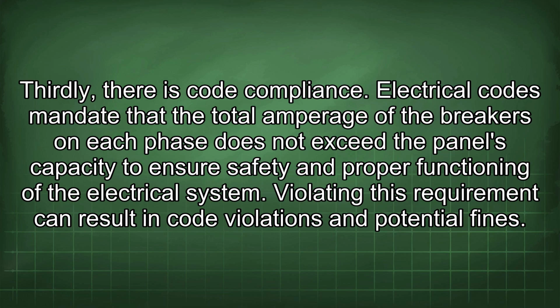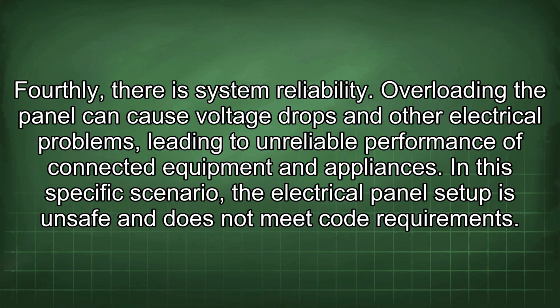Electrical codes mandate that the total amperage of the breakers on each phase does not exceed the panel's capacity to ensure safety and proper functioning of the electrical system. Violating this requirement can result in code violations and potential fines. Fourthly, there is system reliability. Overloading the panel can cause voltage drops and other electrical problems, leading to unreliable performance of connected equipment and appliances.